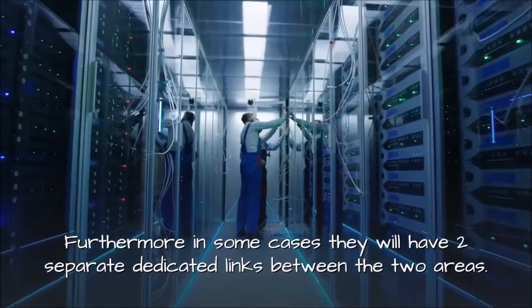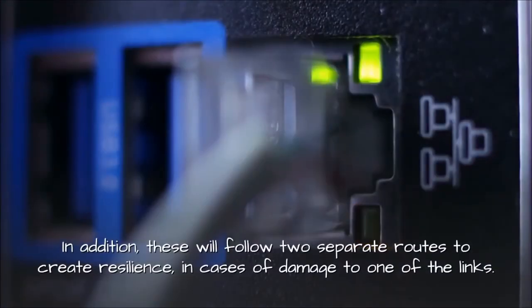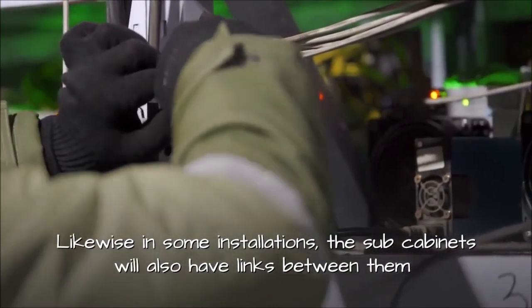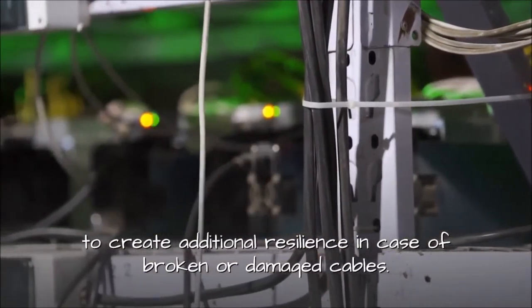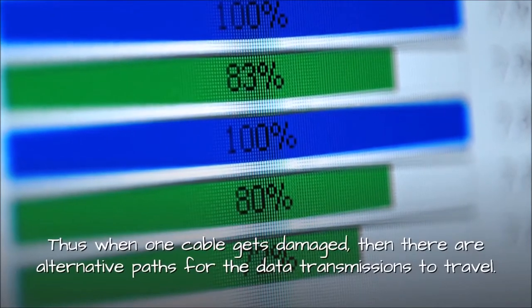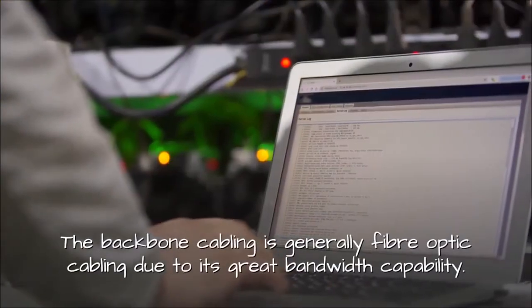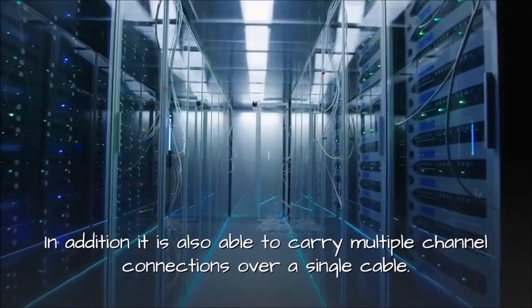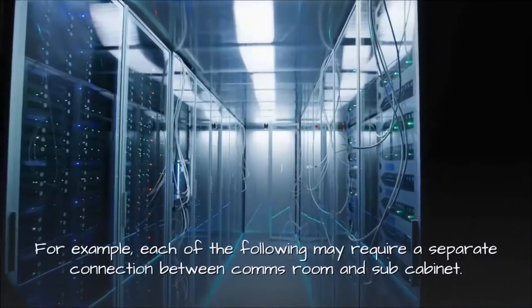Furthermore in some cases they will have two separate dedicated links between the two areas. In addition, these will follow two separate routes to create resilience, in cases of damage to one of the links. Likewise in some installations, the sub cabinets will also have links between them to create additional resilience in case of broken or damaged cables. Thus when one cable gets damaged, then there are alternative paths for the data transmissions to travel. The backbone cabling is generally fiber optic cabling due to its great bandwidth capability. In addition it is also able to carry multiple channel connections over a single cable.